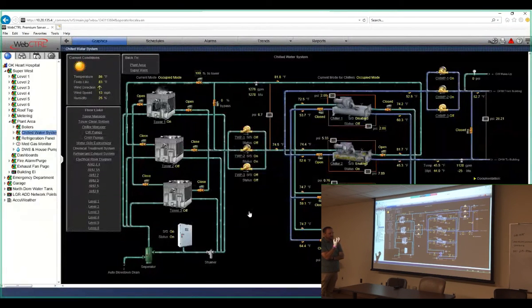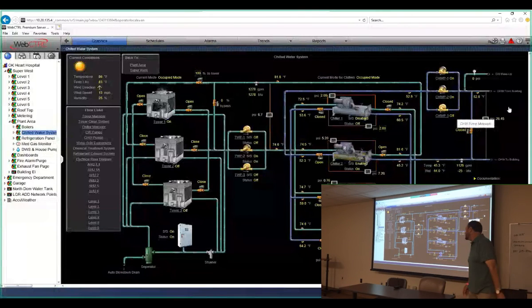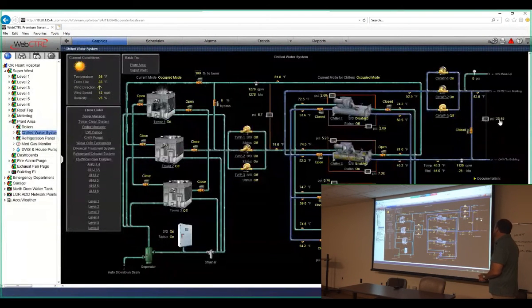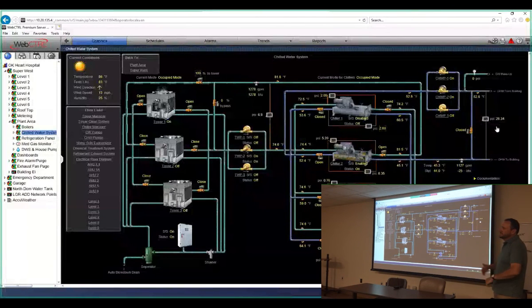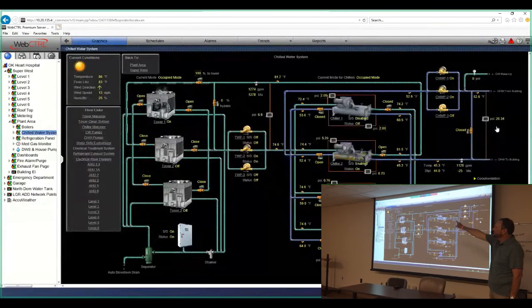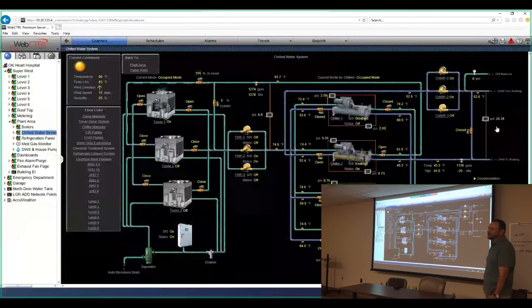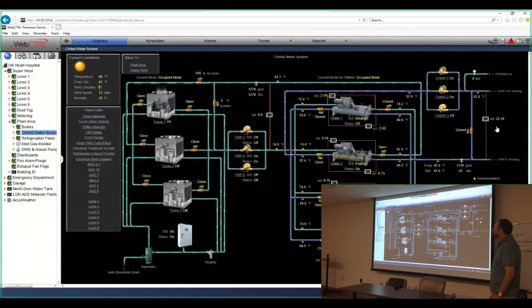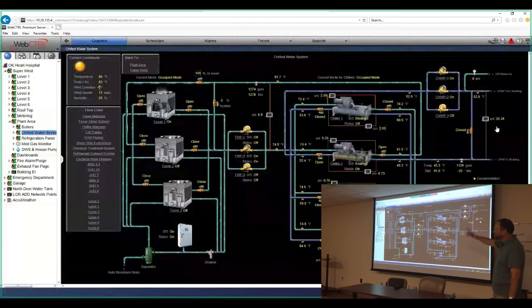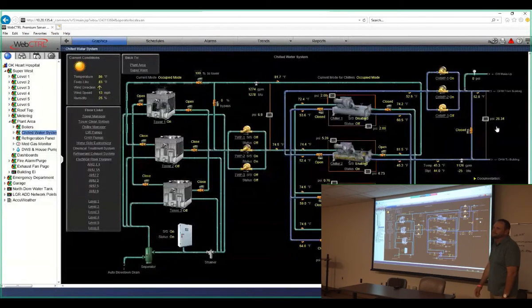Due to the pressure that we need up at the air handling units, if you look right here, this differential pressure is the pressure leaving the plant. It's 26.45. Set point is 27. You're generally going to see 2 chill water pumps running a lot. So you may see 2 chill water pumps, 1 chiller, 1 condenser water pump, and 1 tower for the majority of the operation, it can handle it. When we get into higher loads, you're going to see 2 chill water pumps, 2 chillers, 2 condenser water pumps, and 2 towers. So basically, if we have to bring another chiller on, we need another condenser water pump, and we need another cooling tower. Pretty simple.